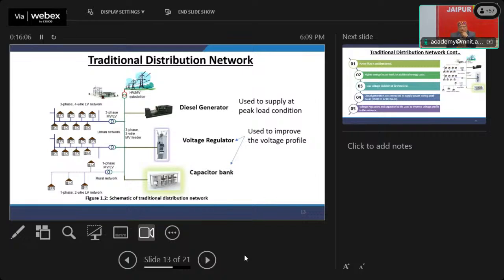Then slowly we came across capacitor banks, voltage regulators, diesel generators as a backup, and this is how the modern system becomes slightly smarter. So the backup power supply from diesel generators, voltage regulators for voltage variations. Why voltage regulators? Because the voltage of this particular bus needs to be maintained at a constant 1.0 per unit, which is 440 volts or 11 kV, and that is not possible because the load keeps on changing. So we need a regulator which can maintain the voltage. And most of the time, the capacitor bank is very important because of reactive power injection.